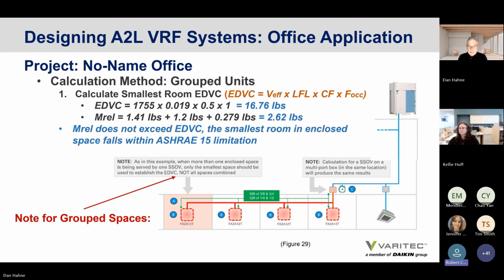Okay, all right, thanks. I was just going to follow up on the other question too about the code review. Not only is the code a static device, as far as how it's memorialized and published, because they're not normally issuing addenda to the codes, but there's a misprint in the code about what the RCL charge is for some of the refrigerants, which is becoming a problem because it lists, I think, 3.2 pounds, not 4.8 pounds. Additionally, they don't get into LFL. It's only RCL, which is not the way that ASHRAE reads it. So there are some differences there too.